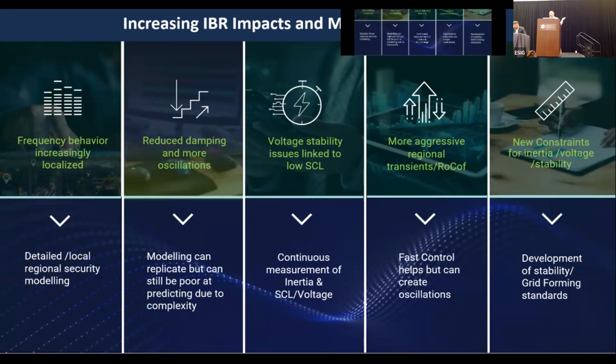We've seen it talked about a number of times, mentioned this morning in the grid forming session - increased problems with voltage stability. We've seen this on the ERCOT system as well, linked to the fact that most of this is IBR running, with reduced short circuit level associated with that. So we provide continuous measurement of short circuit level at a substation, based on a small voltage probe into that substation.